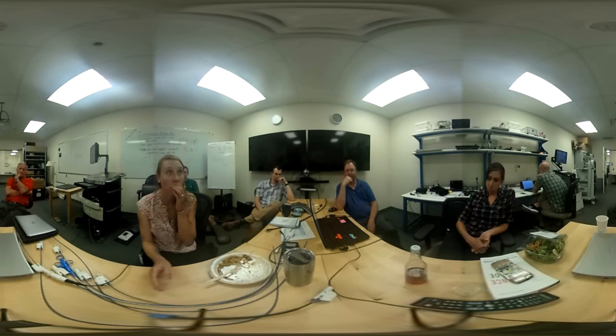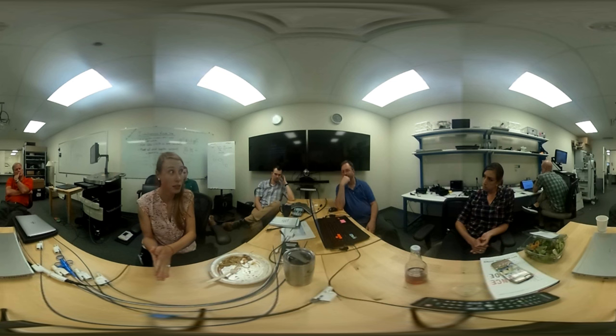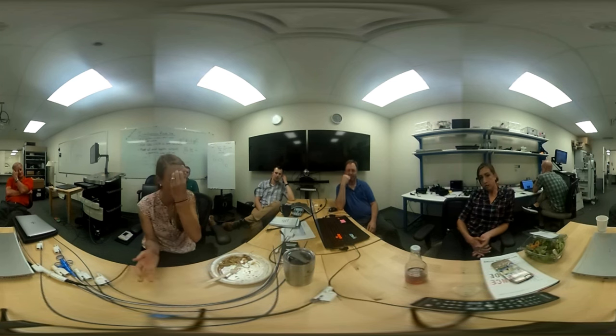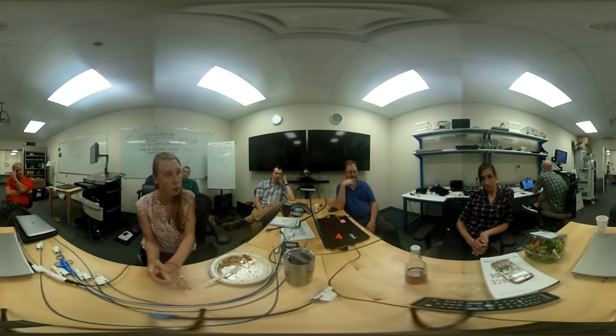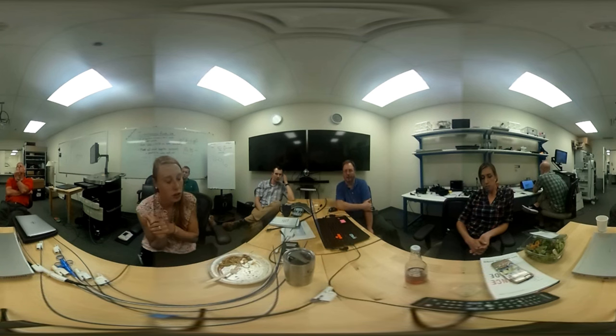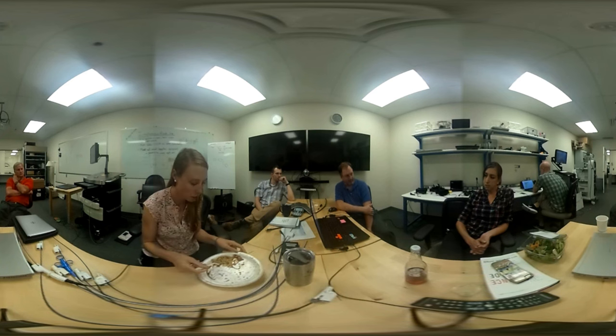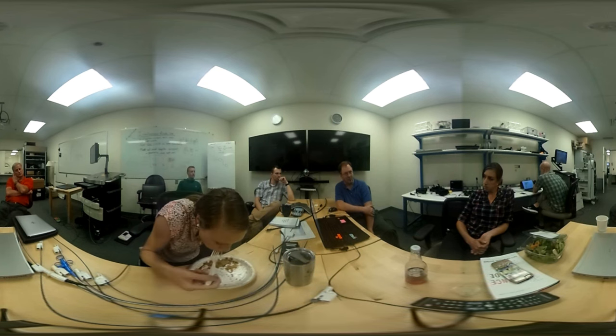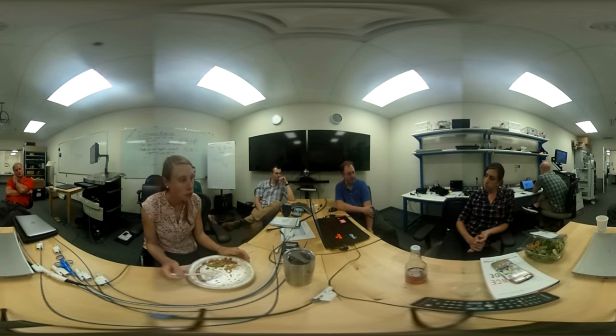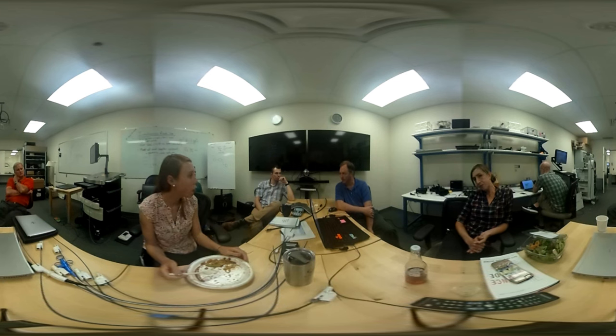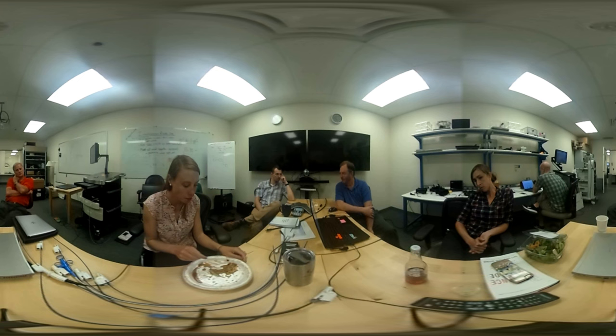So what do you think we're missing? Is it possible that something would happen to the catheter such that it's not accurate anymore, but we could still pass our calibration threshold? Because if it gets damaged, then it's really gonna fail our gain limit or fail the offset. Then there's no need to put a second spec on how much it's really gonna change if these are failed. The software is set up to do this already. Right now, you choose what your angle is, and it says go to this cal point. We're trying to separate the variation of this. And if we wanted everything to be identical, we could still do the curve, and we could just check position.